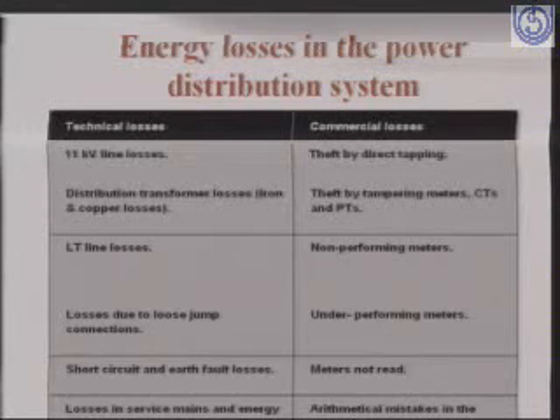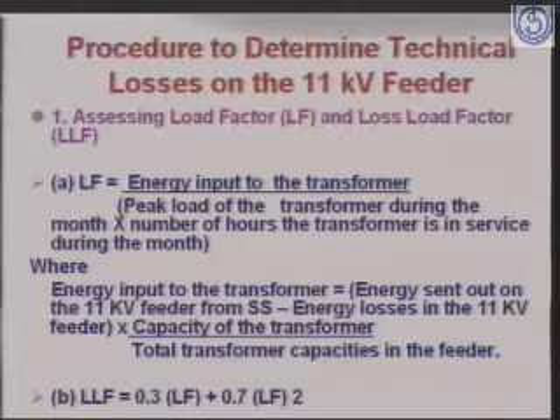And in the commercial losses category, we have theft by direct tapping, theft by tampering with meters, current transformers and potential transformers. Then we have non-performing meters, underperforming meters, meters which are not being read, and arithmetical mistakes in the billing. All these losses together are clubbed as commercial losses, because these are the units which are lost, for which no revenue is being generated by a utility.